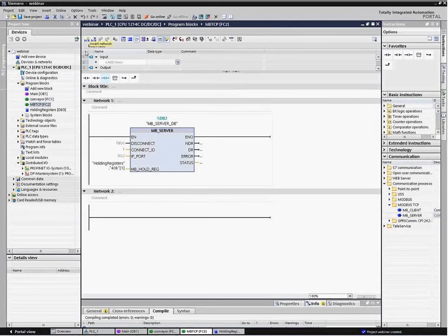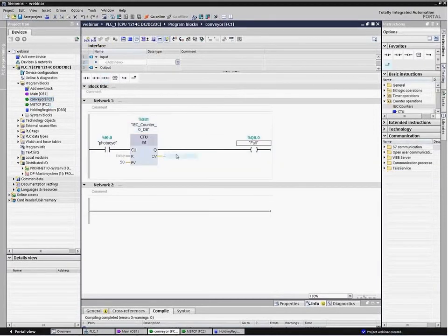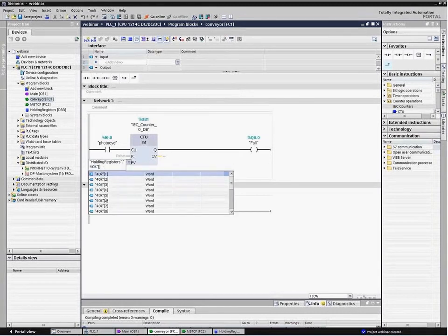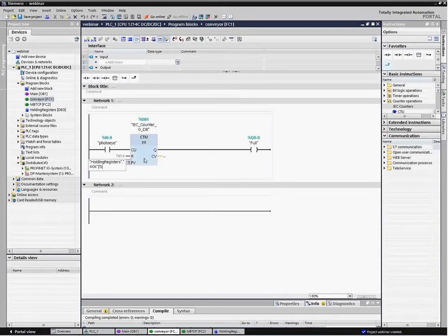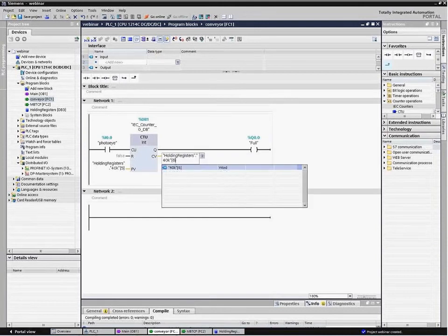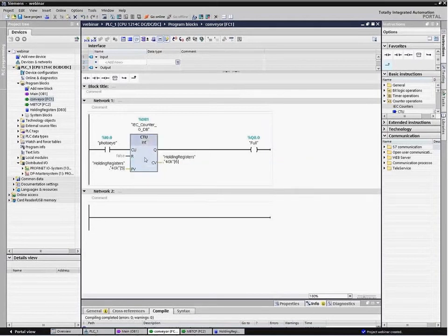What else do we need to do to implement our Modbus TCP? We mentioned that we wanted to use the preset value, current value, and put that into Modbus. So if we're to do that, I'm just going to go back into holding registers and say we want 40,005 to be the preset for our counter. Current value that we could read to the SCADA system, 40,006. Could be anything we want in there. Then effectively we've mapped in these two variables into Modbus.